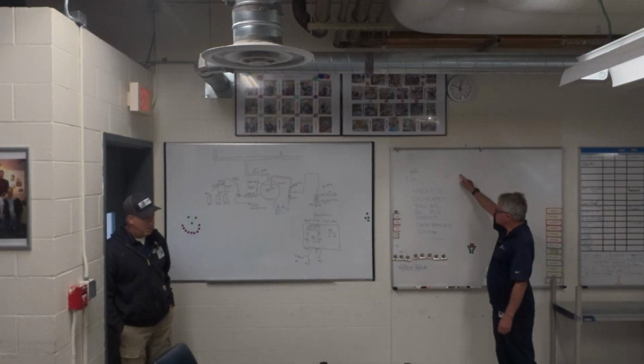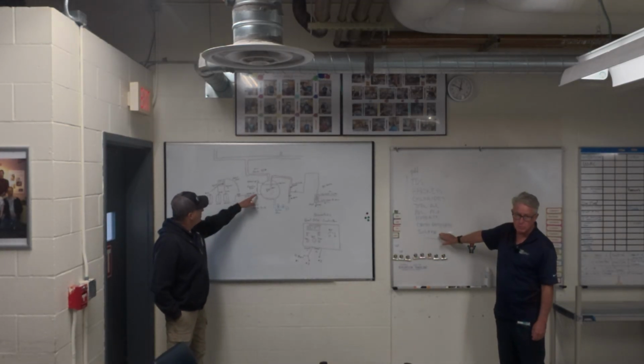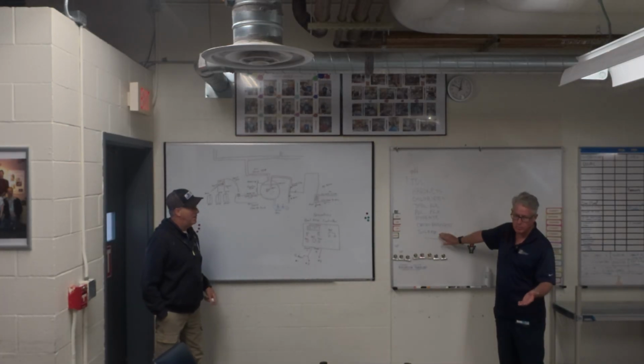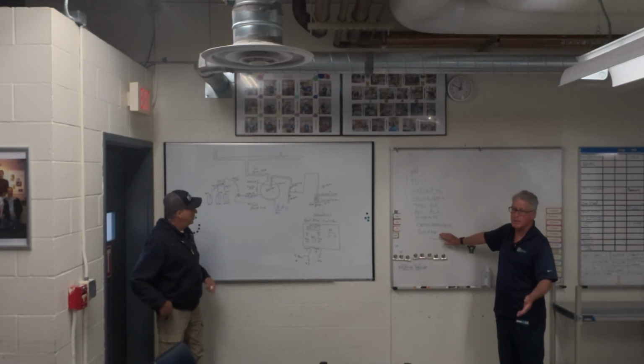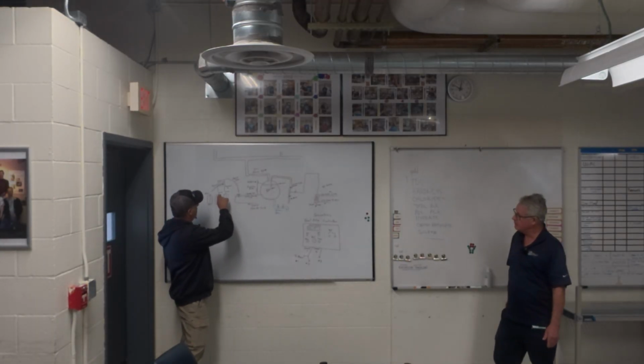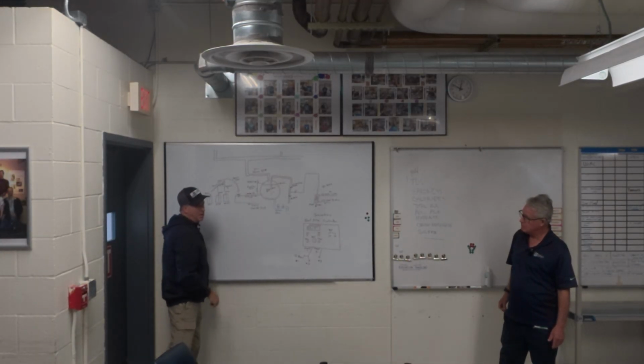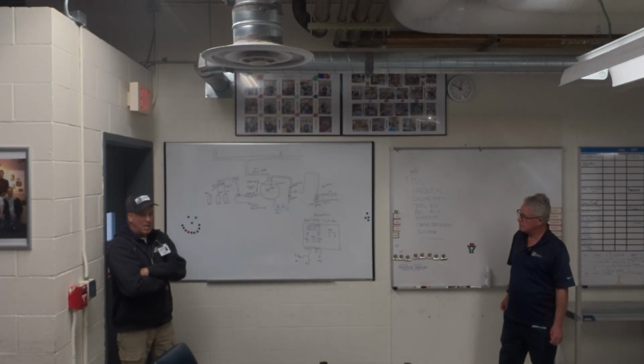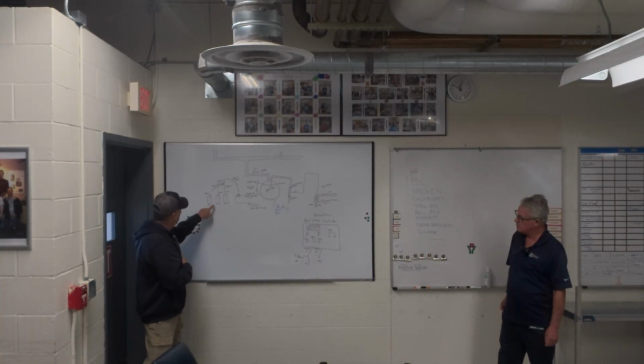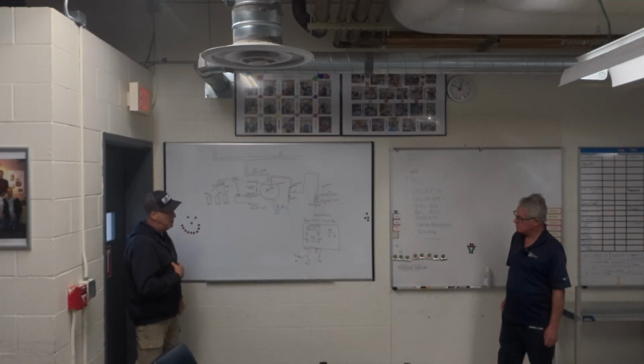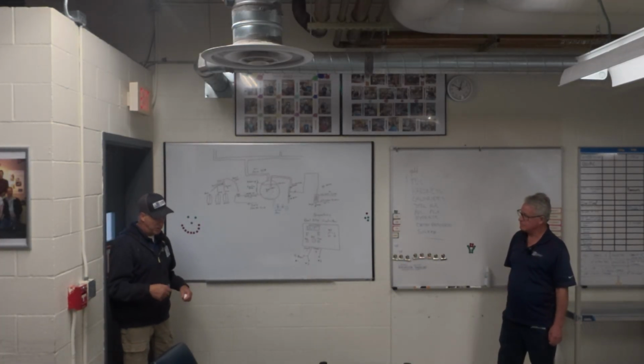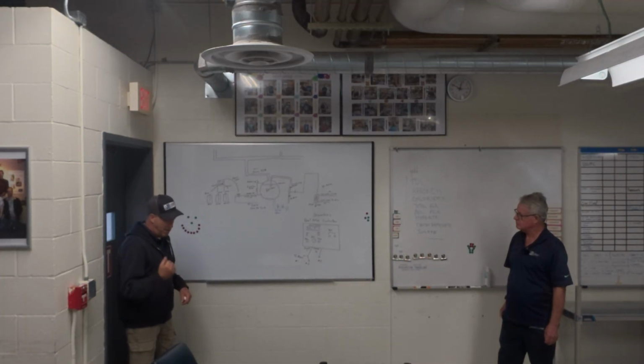When we do these tests, we can identify, let's say sulfites are low. We can go take a look at the sulfite OX21 pump and say, is the thing plugged? Is the barrel dry? You're talking about a physical obstruction between the fluid of the pump and its way into the quill, into the loop. Yeah, I noticed you get a little scale buildup. In the past, we've had different little tubes and stuff plugged up. Yeah, there can be little crystals that develop in there and foul up the works, particularly in the suction of the OX21. But we have such a mixture now that it's not as likely to do that, but if it does, let us know. In the meantime, you can just add some warm water in there and stir it around. Some of those crystals may go into solution, and then you can pull on the suction tubing a little bit and get that freed up so it starts pulsing again.